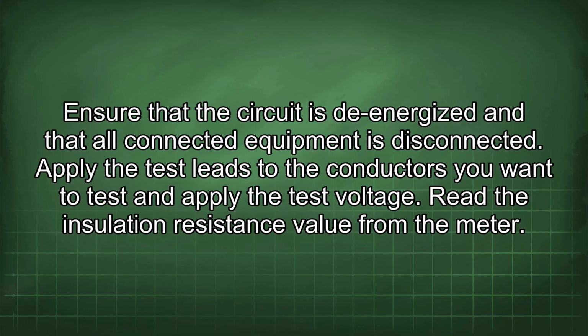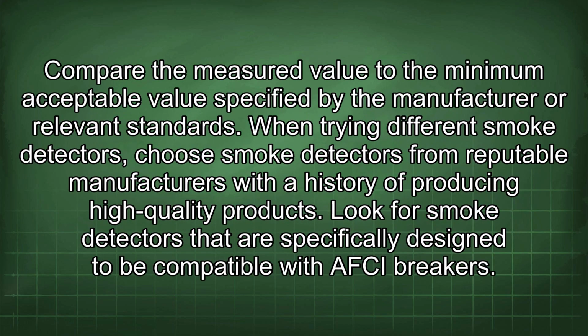Ensure that the circuit is de-energized and that all connected equipment is disconnected. Apply the test leads to the conductors you want to test and apply the test voltage. Read the insulation resistance value from the meter. Compare the measured value to the minimum acceptable value specified by the manufacturer or relevant standards.